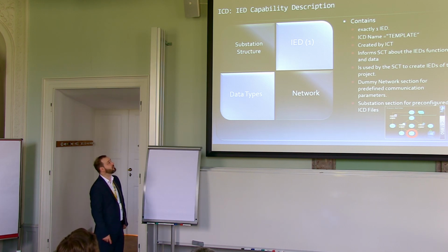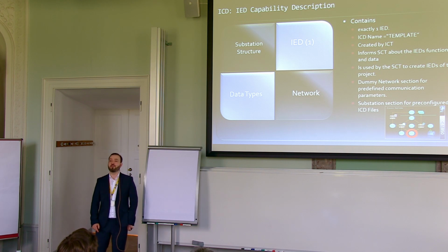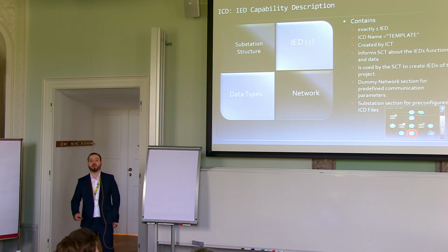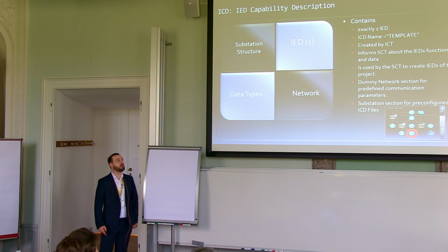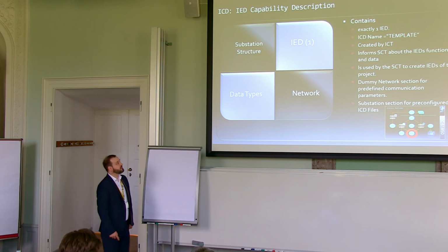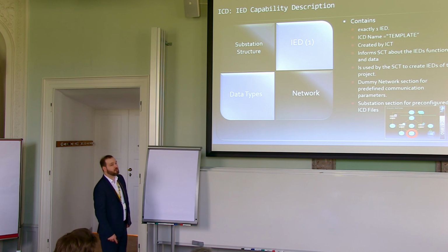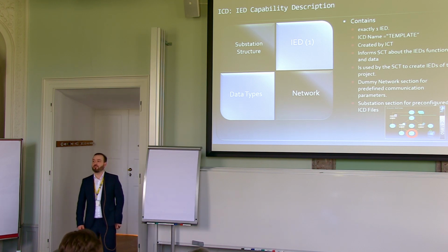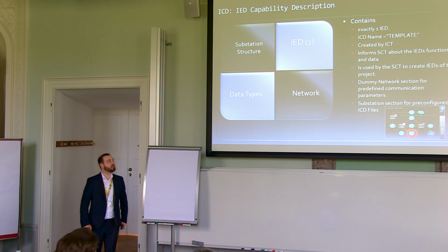Sometimes you get files that claim they are ICD, but may have multiple IEDs in there, or they don't have any that are named template. And in that case, your tool can't really make an informed decision about what you want to do with this file. It's not getting what it expects.